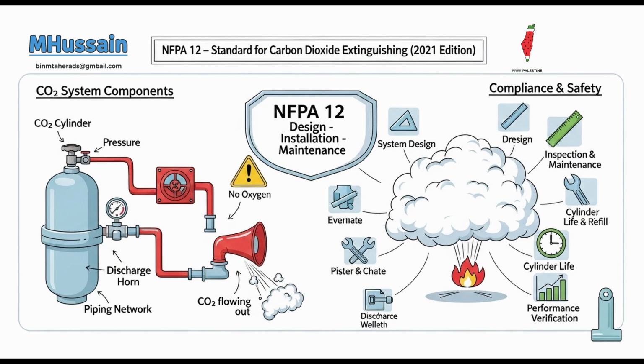Plans must be prepared by qualified personnel and submitted to the authority having jurisdiction, AHJ, before any installation begins. These detailed plans must include comprehensive information on the hazard, precise CO2 quantities, exact nozzle and pipe locations, detection and control specifics. Everything documented. And if any changes occur during installation, as-built drawings must be meticulously prepared. The system owner is ultimately responsible for maintaining a comprehensive instruction and maintenance manual, which is the system's ongoing Bible. Owner keeps the manual. What about approving the installation?